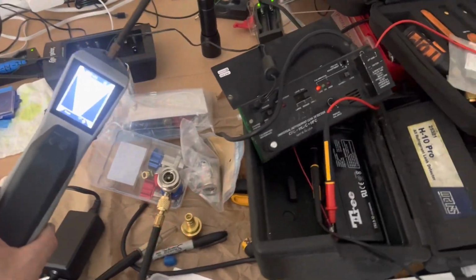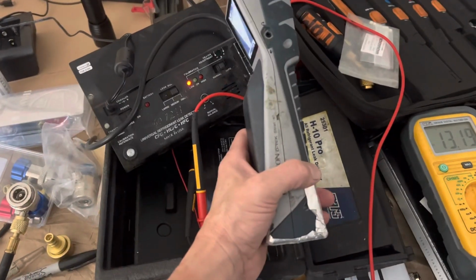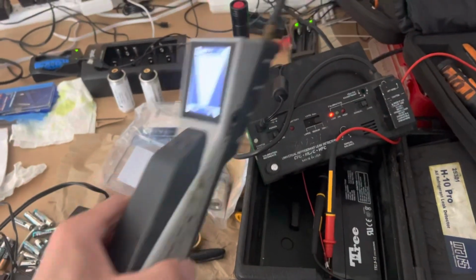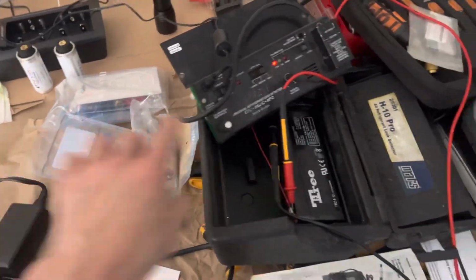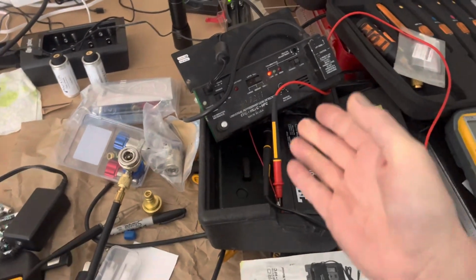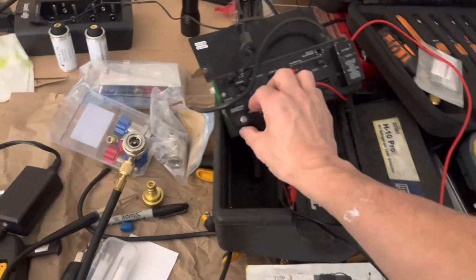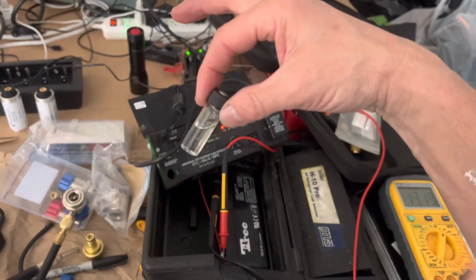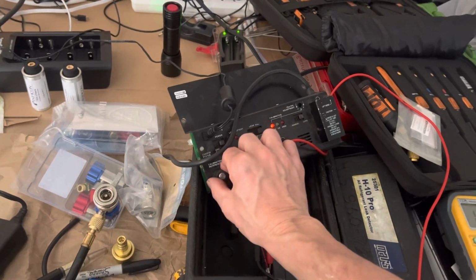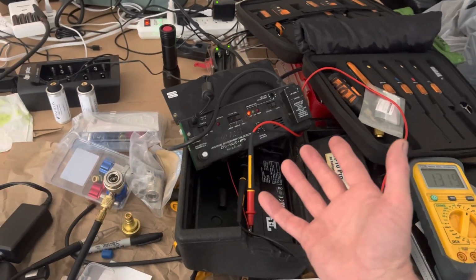Comparison and sensor adjustment of the H10 Pro right there. This is the Stratus in my hand. Now the H10 Pro, unlike most leak detectors, comes with a refrigerant calibration bottle to check that your sensor is accurate and sensitive. Other refrigerant leak detectors do not.